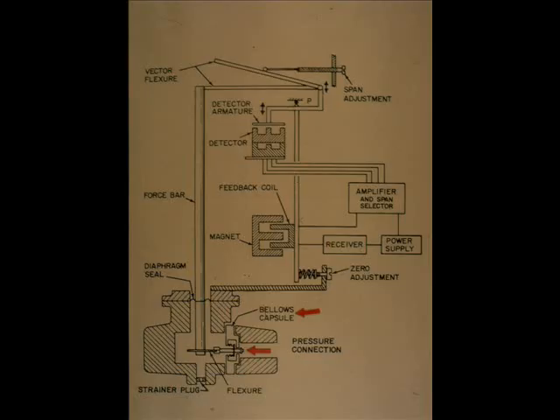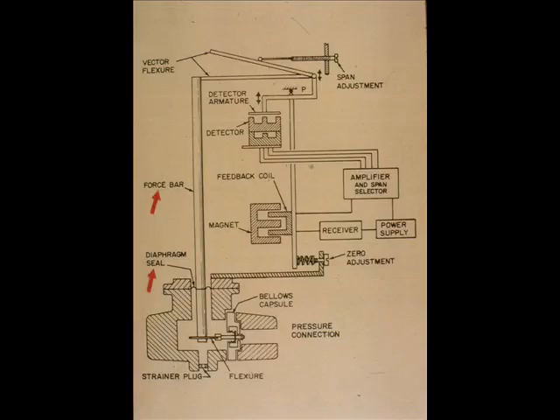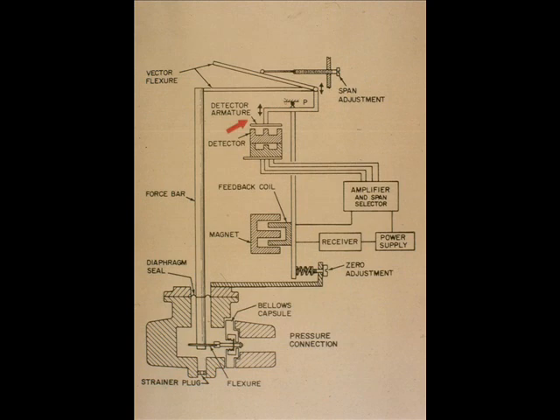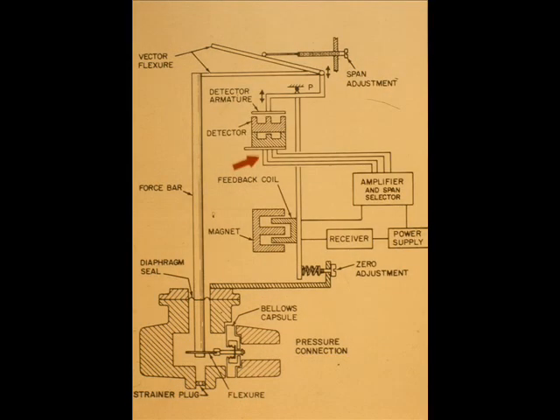The pressure exerts a force on the capsule, causing the force bar to pivot about the diaphragm seal. This causes a movement of the detector armature, which causes a change in current flow in the detector secondary winding.